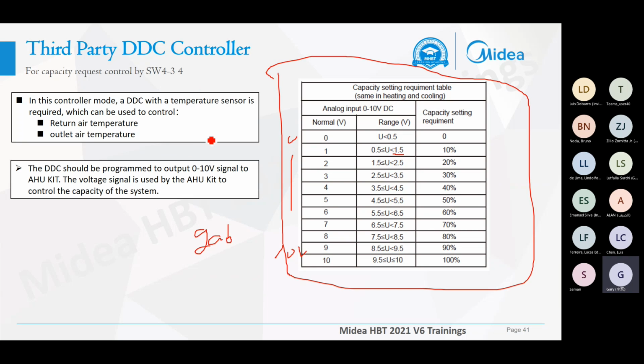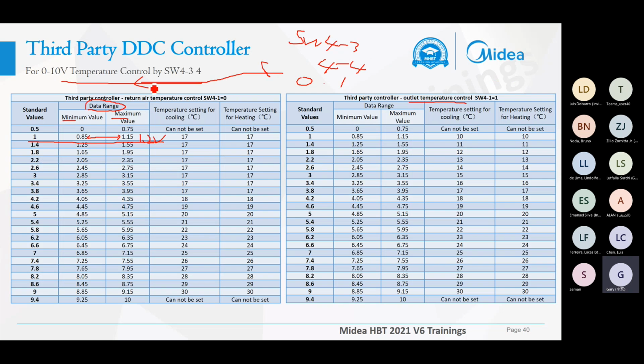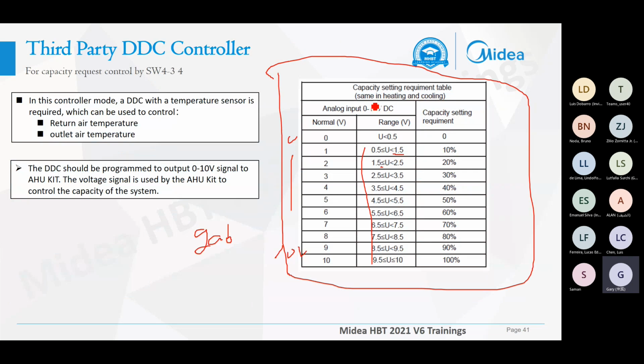But in this capacity control, they don't have any gap. They all have continuous control, just like 0.5 should be less than or equal to, and less than 1.5 volts. But from 1.5, it has the equal to. If you have equal to, this is continuous. There is no gap for the control signal. This is the big difference between the temperature control and the capacity control.